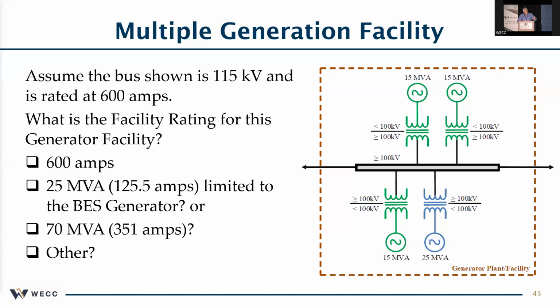So I said, let's make the assumptions 115 kV, so it is BES on that bus. That bus is 600 amps. The BES definition document doesn't go into those details. And I said, so what was the rating for this generator facility? And it was kind of interesting. It wasn't really intended as a trick question, but it really is a little bit thought-provoking. Every auditor except one said 600 amps. But then I'm thinking, well, what about that most limiting component thing?